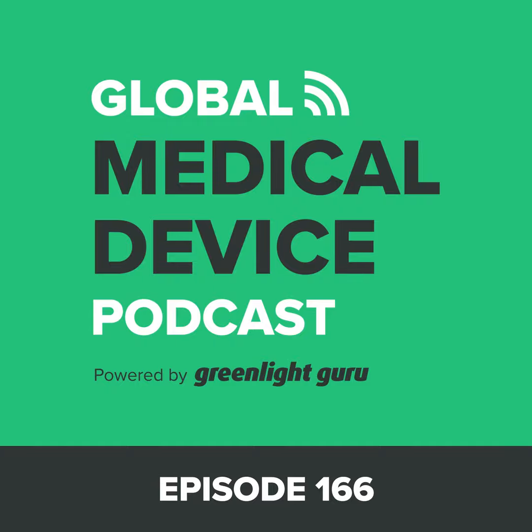Well, let me just say this, Jon. When it comes to biocompatibility and risk mitigation via a variety of methods, including purchasing controls, this is obviously a complicated topic, and we could probably have a discussion just on that in the future if you wanted to. Yeah, we could. But let me be clear, I'm not suggesting that we should not use purchasing controls as a form of risk mitigation here for biocomp. We can. We just have to be careful in, as you just alluded to, Jon, the details of how we do it. And it should also not be, in my opinion, the principal, or certainly not the only way that we mitigate risk in this case.